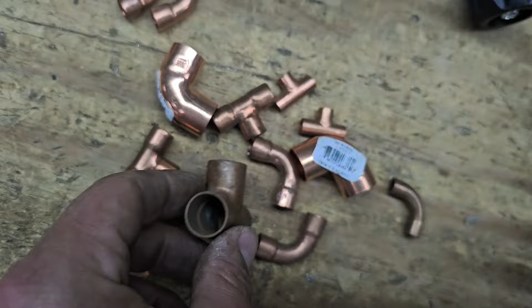Then we're going to start installing some fittings. I've got 5/8 T's, 3/8 T's, 1/4 inch T's. And we're going to have an inlet and an outlet. And our inlet is probably going to be at the top and our outlet's probably going to be at the bottom, or vice versa. I'm not sure yet, but I know that we're probably going to have 1/4 inch copper coming in, and we're going to have 5/8 copper going out. I'm going to start the brazing process, and let's go ahead and turn this into a coil.